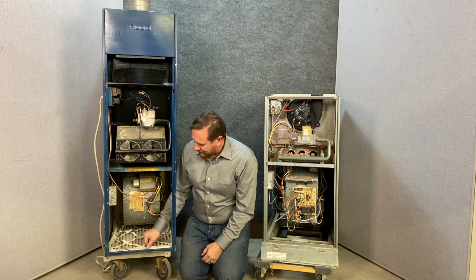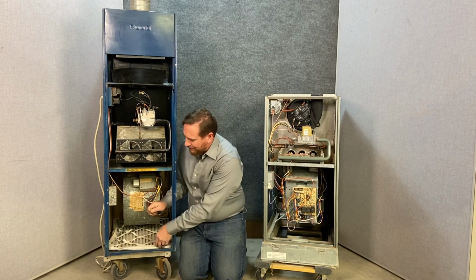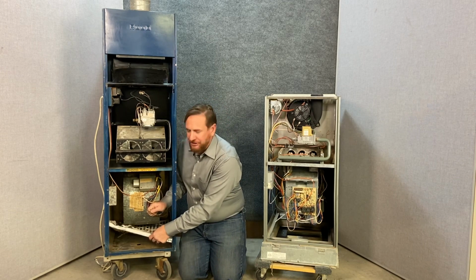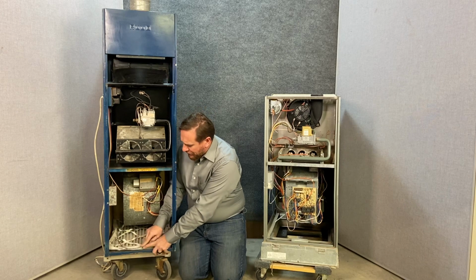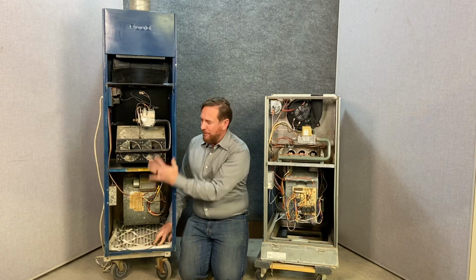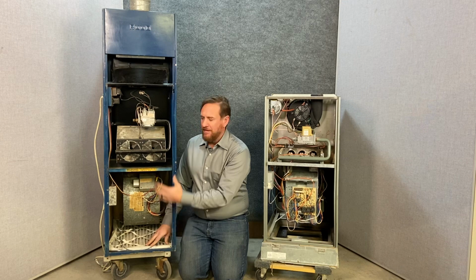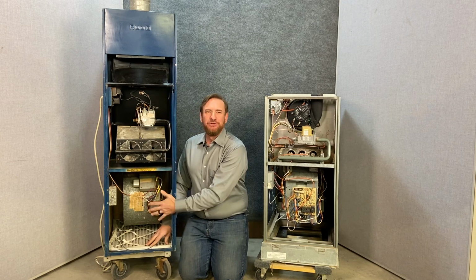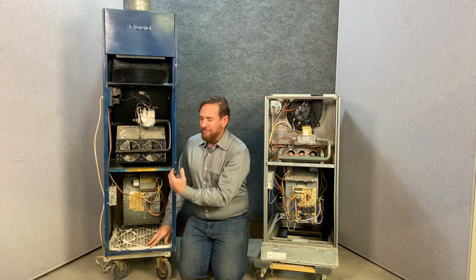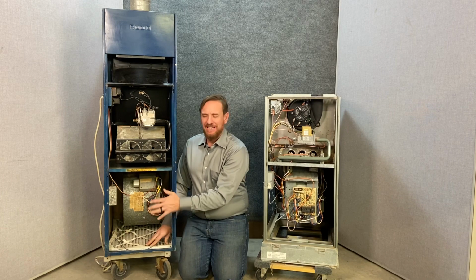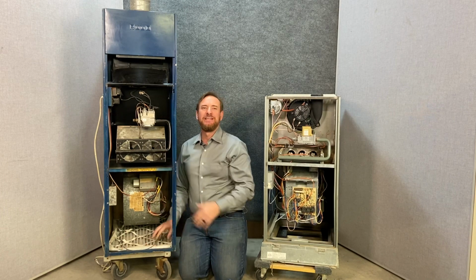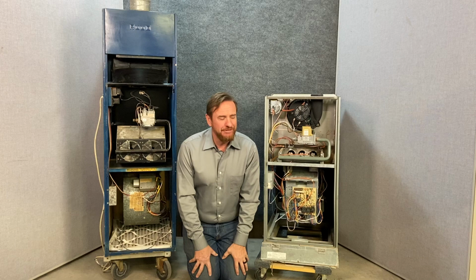On this old furnace, we have this little wire mesh and this old filter that you would slide out. So the customer had to take this door off, both doors off, to change the filter all the time. So it was a huge issue with that door not being put on correctly, or them leaving the door off so that they wouldn't have to go through all that mess. And people have been sick and died from that.